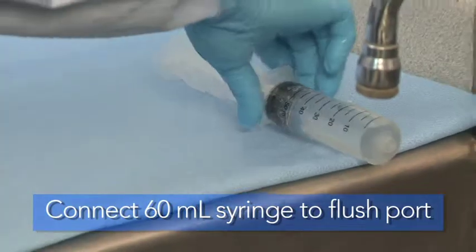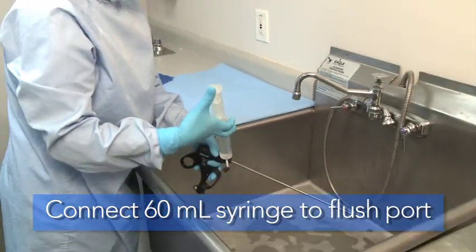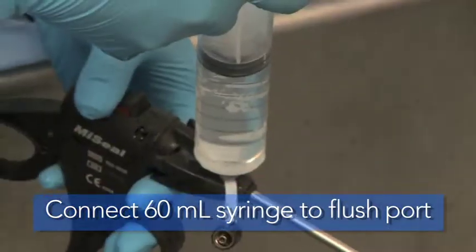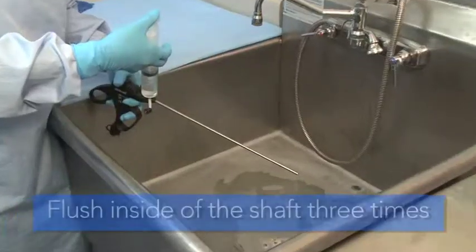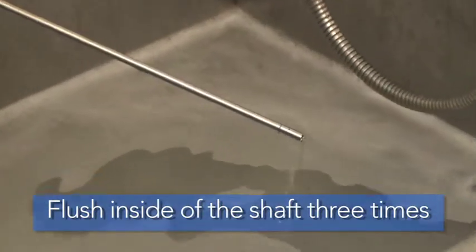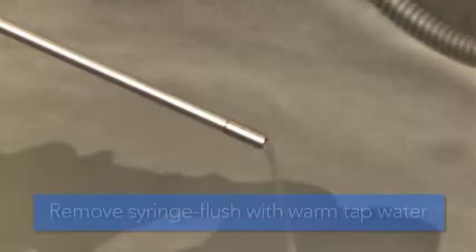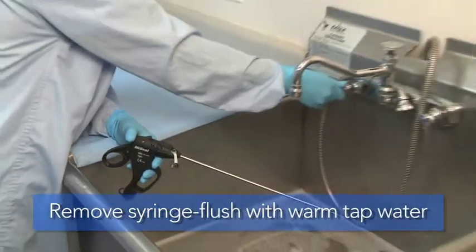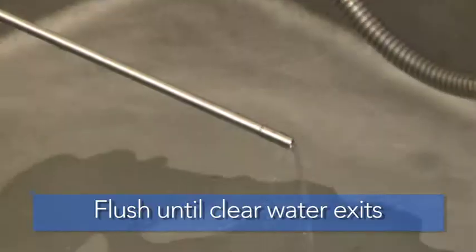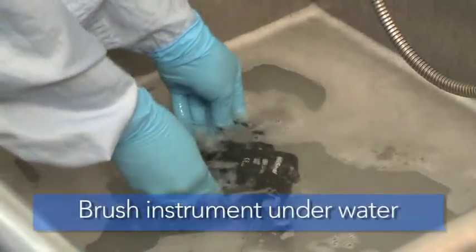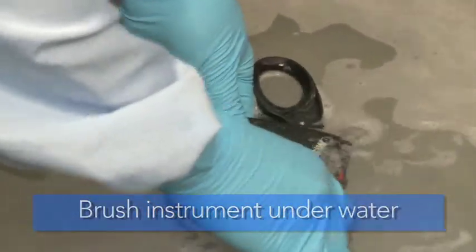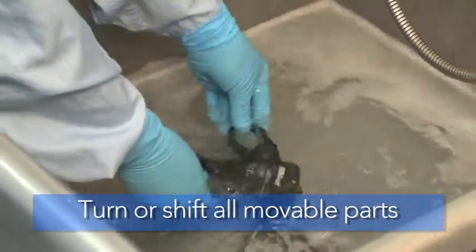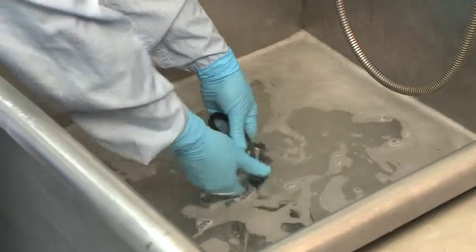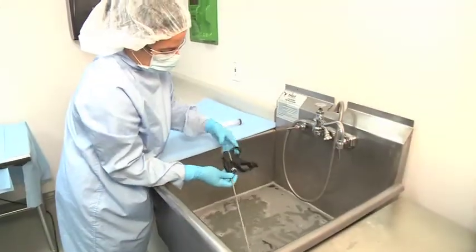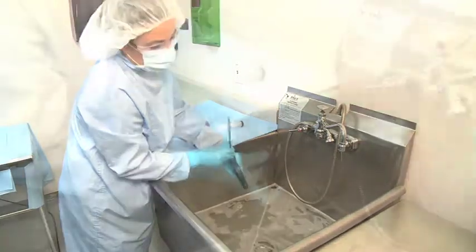Connect a 60 milliliter Luer-type syringe filled with the prepared enzymatic solution to the flush port where the Luer cap was removed. Using the syringe, flush the inside of the shaft 3 times. Remove the syringe and repeat flushing with warm tap water. Flush until clear water exits. Brush the instrument underwater to avoid airborne contaminants. All movable parts must be turned or shifted underwater, including the triggers and rotator knob. Make sure that all visible bioburden is removed.